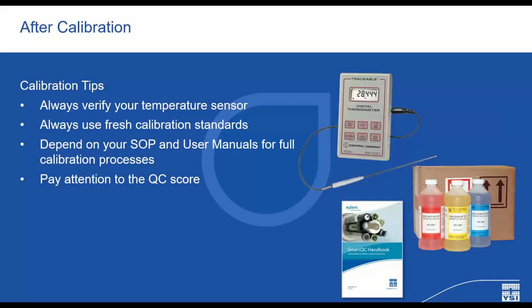I realize once again that we've been over a lot of info here. Key takeaways from this particular section: always verify your temperature sensor. That's the #1 thing to start with. If it's faulty and you don't catch it up front, all of your other time and efforts will be wasted. Always use fresh calibration standards. Depend on your SOP and the operator's manual for step-by-step calibration processes, and pay attention to the QC score and the help that it provides when completing the calibration process.